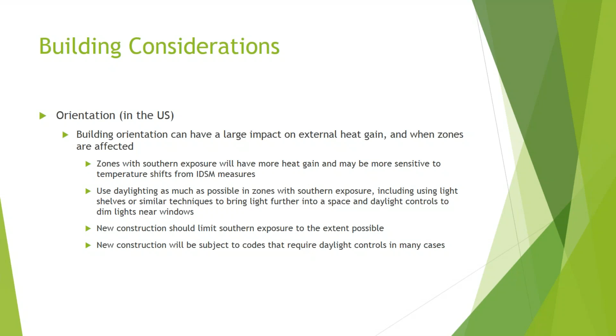Shading can also be very important. There are many sites looking at going to a zero net energy strategy, and if those buildings are being shaded by other buildings, trees, or here in Southern Nevada, mountains, that can affect your choice of integrated demand side management strategy. So you could have limitations on the use of solar, and you have to account for shading effects because, of course, lower floors are going to see more shading than upper floors, so you may need different DSM strategies for each of the floors.